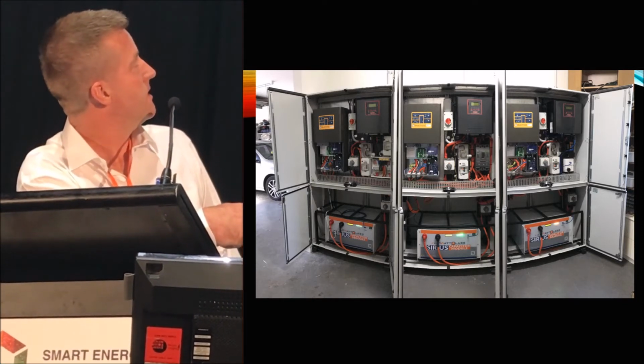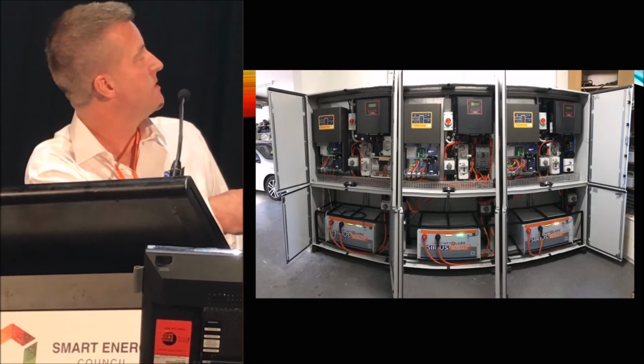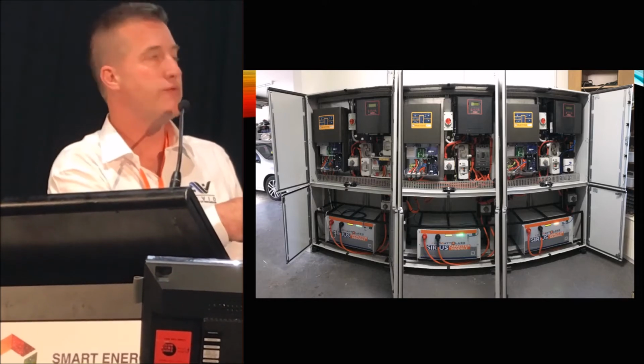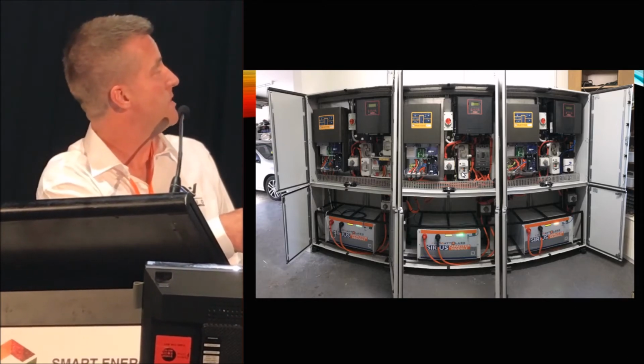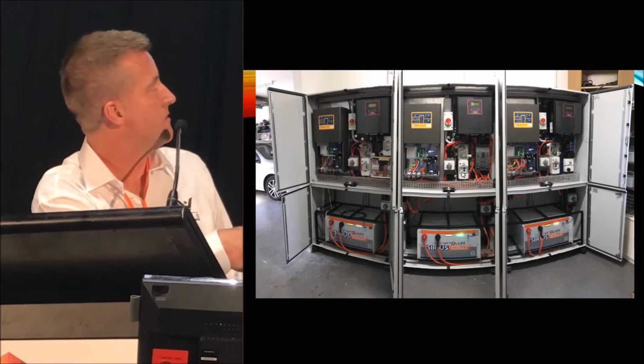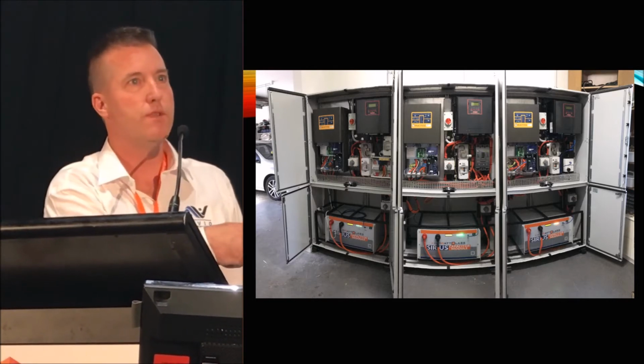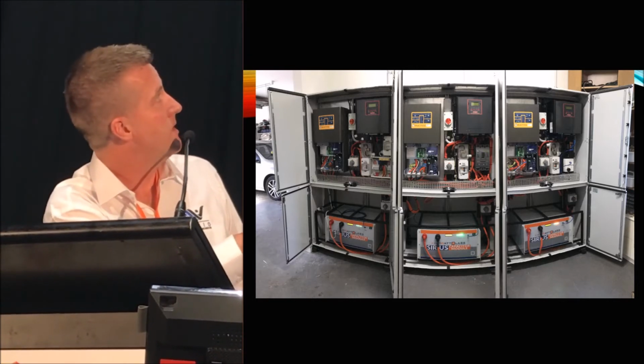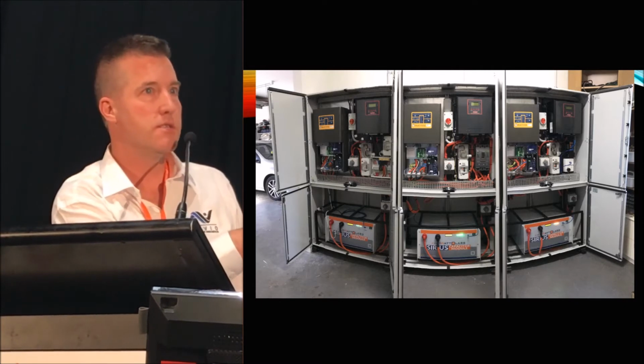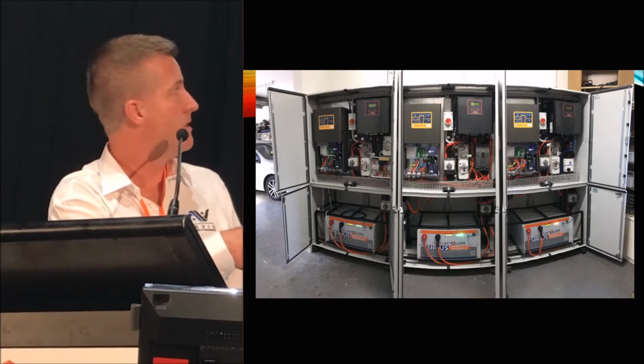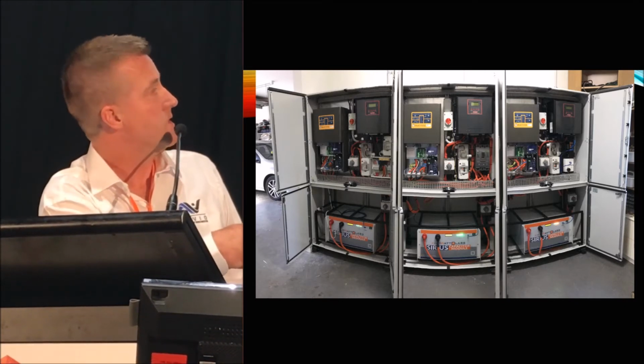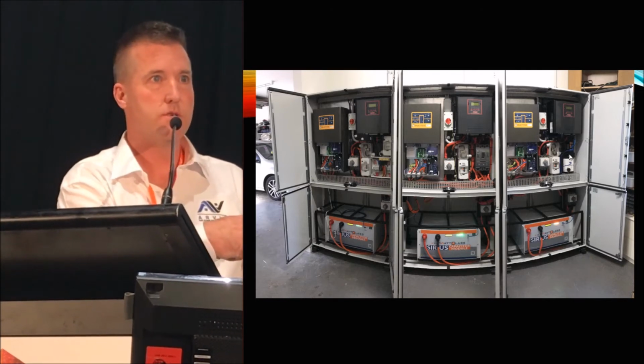We've got small switches here to control the thermofan. So the DC charge controller controls the thermofan. So if it detects a cabin temperature of above 45 degrees, it turns the fan on until the temperature falls to 35 degrees. And you can set that up in the charge controller. You can set the start and stop points for the fan. And this is the same charge controller that you can get as a 120 volt version.